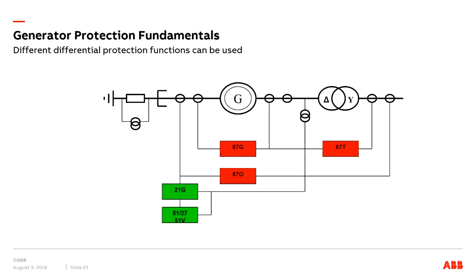So here is a scheme. There are different differential protection schemes possible. One is 87G for the generator itself, the other is 87T, which is for the unit transformer, the step-up transformer, and then 87O, an overall differential protection, which looks at the current comparison. So this overall scheme has a protection zone comprising both the generator and the transformer.